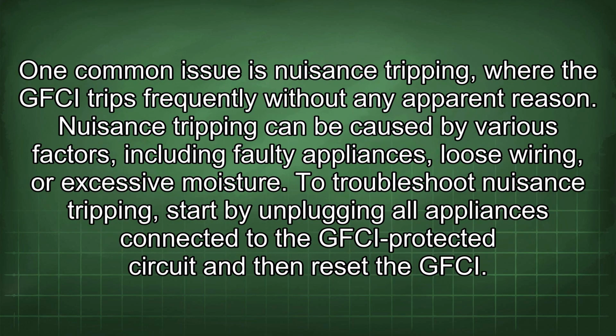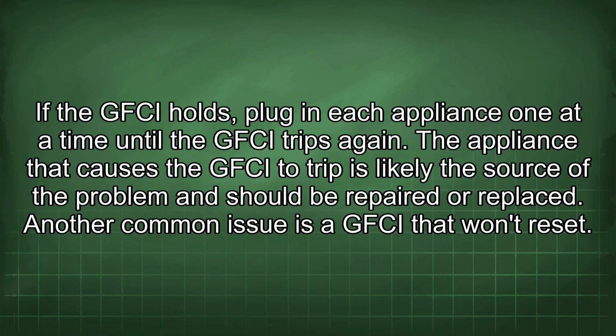One common issue is nuisance tripping, where the GFCI trips frequently without any apparent reason. Nuisance tripping can be caused by various factors, including faulty appliances, loose wiring, or excessive moisture. To troubleshoot nuisance tripping, start by unplugging all appliances connected to the GFCI protected circuit and then reset the GFCI. If the GFCI holds, plug in each appliance one at a time until the GFCI trips again. The appliance that causes the GFCI to trip is likely the source of the problem and should be repaired or replaced.